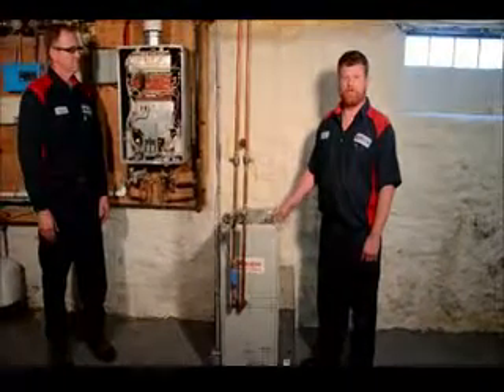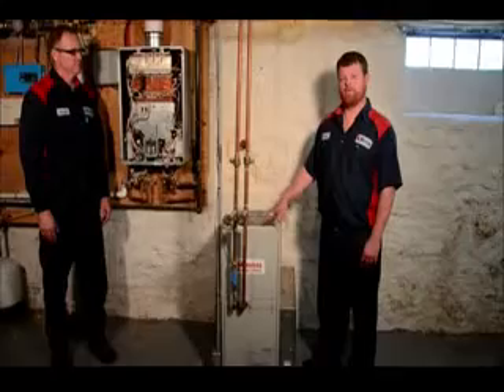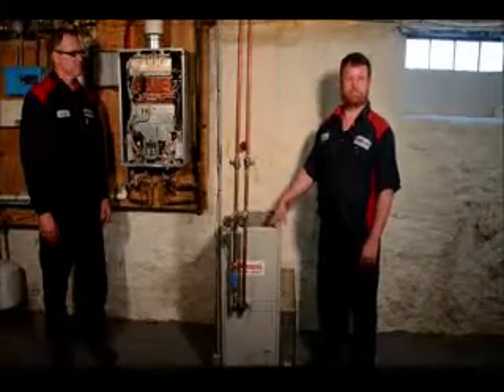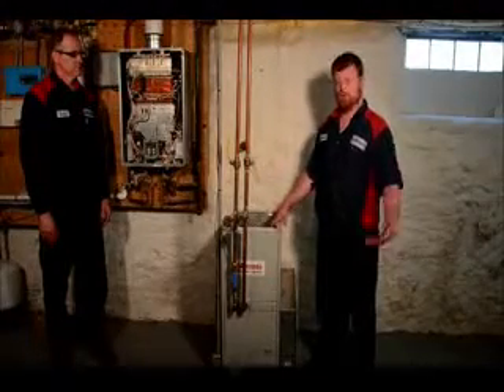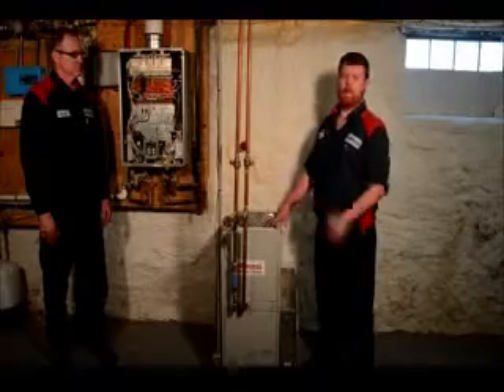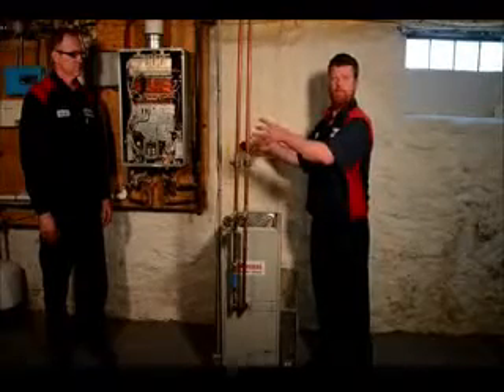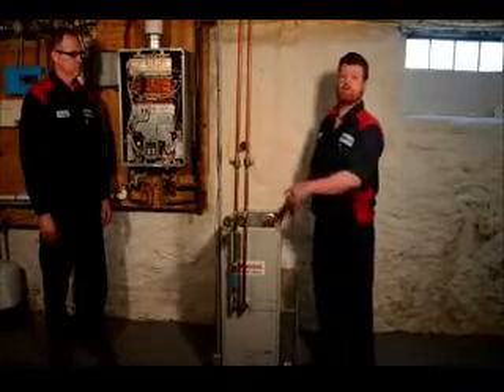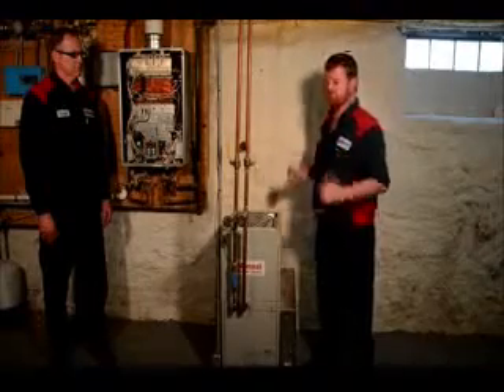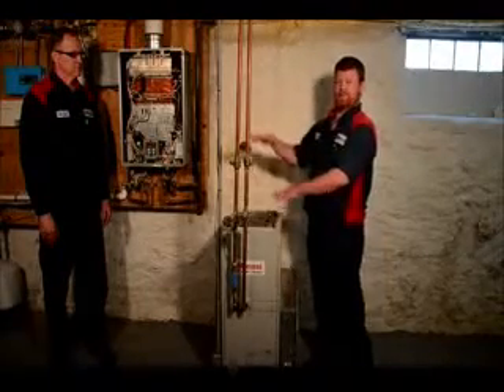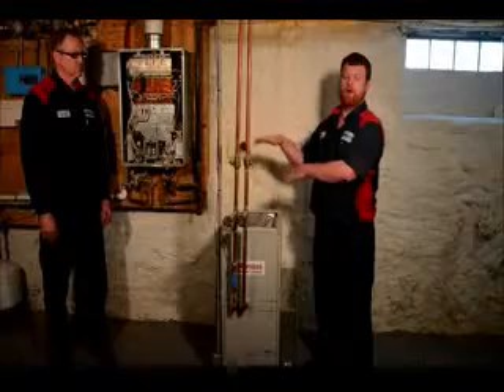This is the Rinnai hydronic furnace. It is a flow-driven furnace. It has a coil in it similar to a radiator coil on a boiler, with a forced air fan from underneath to blow air into your normal plenum ductwork. What we do with this furnace is we take your old furnace out, we shove this furnace in, and you can still use the existing A coil for your air conditioner on top.